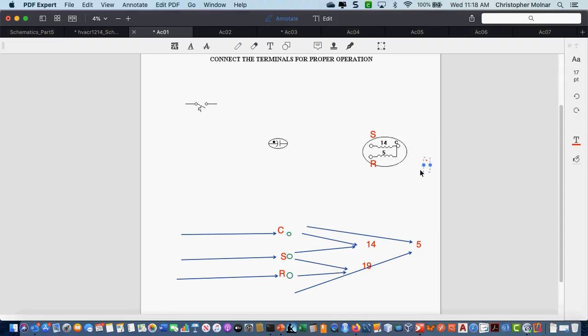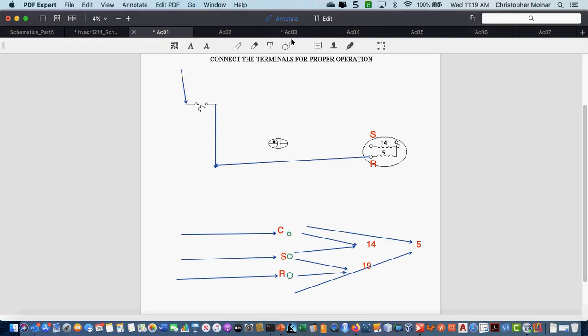Okay. So let's wire our motor here. Let's wire our diagram. There's 2 rules with motors that you can always remember. Run winding always gets full power. 99.9% of the time, there's nothing in series that's a load with the run winding. So when I'm wiring this, the first thing you want to do is power your thermostat, and then come out of your thermostat with line. Your run winding always gets line voltage. There's nothing ever in series with your run winding.